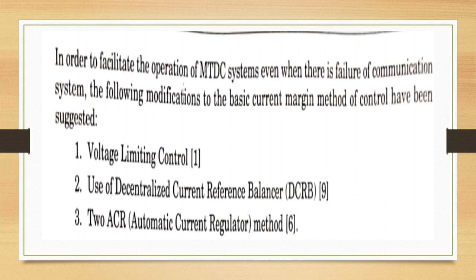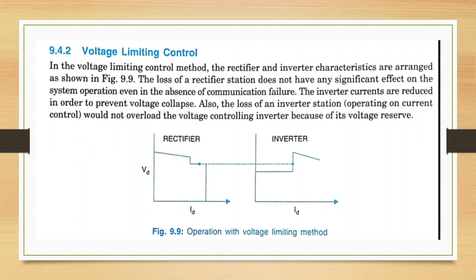Loss of a rectifier station does not have any significant effect on the system operation, even in the absence of communication failure. Inverter currents are reduced in order to prevent voltage collapse. Also, the loss of an inverter station operating on current control would not overload the voltage controlling inverter because of its voltage reserve.